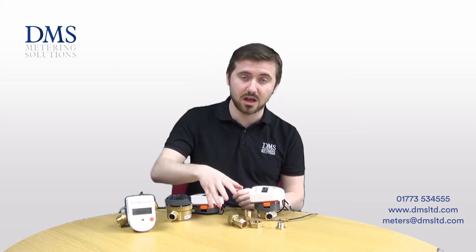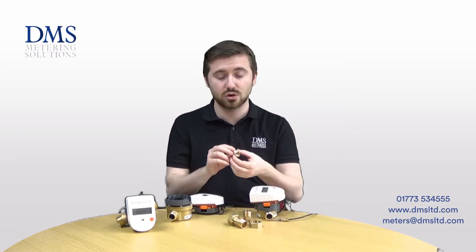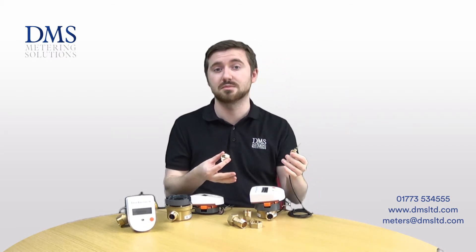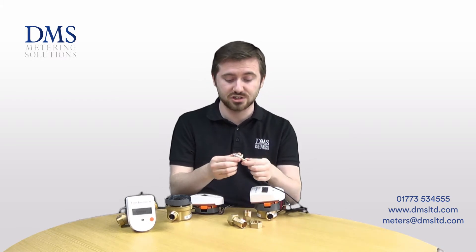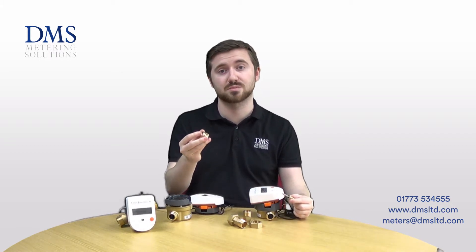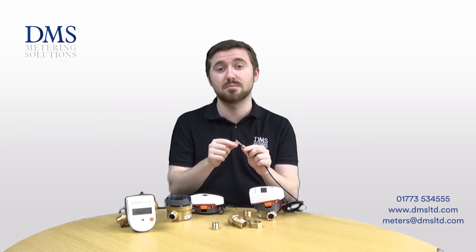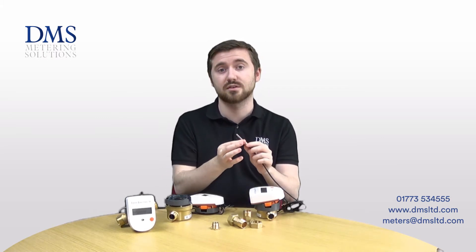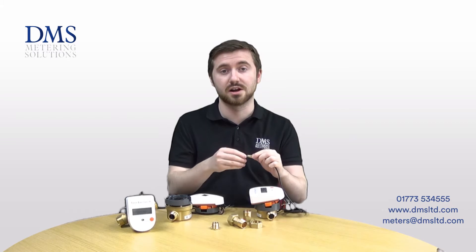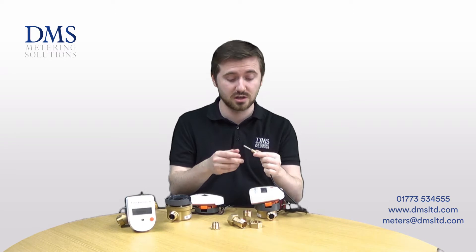The meters are all supplied with a pair of unions as standard for the installation of the body. Each meter is also supplied with a direct mount sensor adapter — this just means that your sensor that is not mounted in the meter body has a much smaller connection than is standard with UK markets, so this actually provides a half inch male BSP thread. If you wanted to install the sensor on its own, that is also fine — this is just an M10 male thread on the neck of the meter. This can also be supplied as a plastic fitting as a small cost saving, but brass is normally the standard based on standard temperatures incurred.